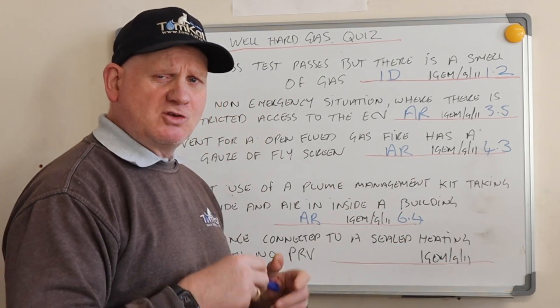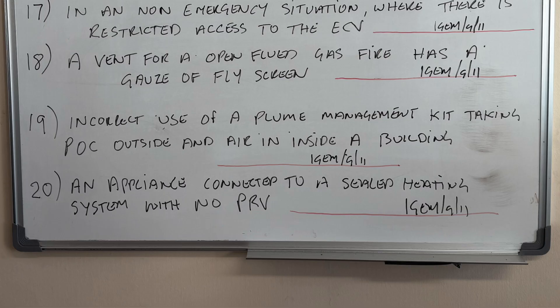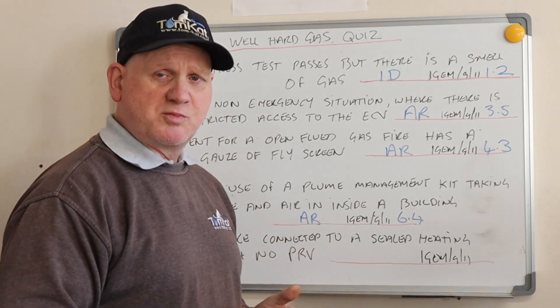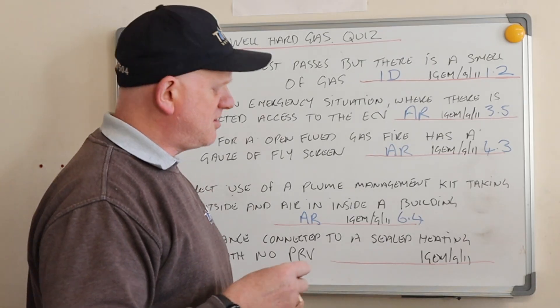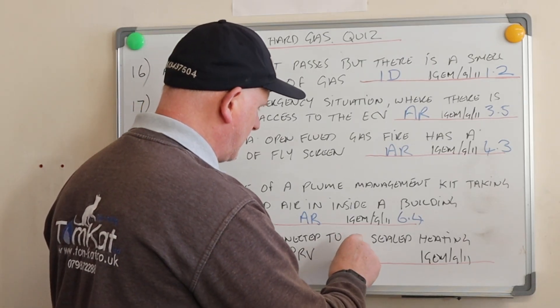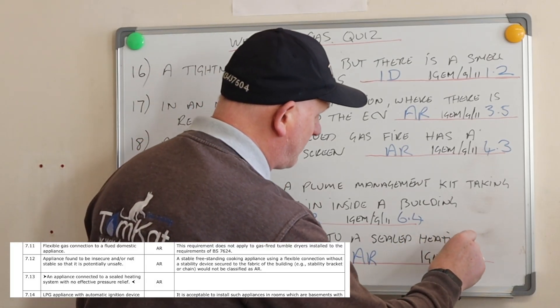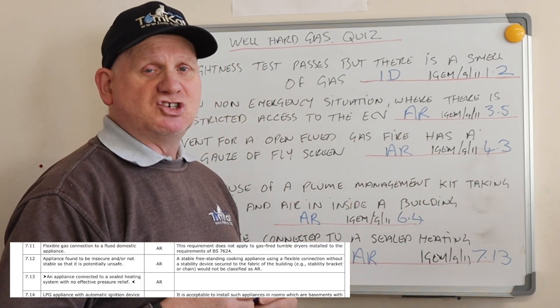Final question: an appliance connected to a sealed heating system with no pressure relief valve — a boiler connected to a sealed system with no pressure relief valve. If you classed it as ID, you'd be wrong, because again it's 'at risk,' and it's at section 7.13 in IGEM G11.